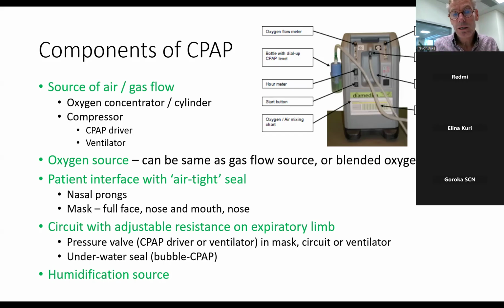You need a patient interface with a relatively airtight seal, and they can be, as I said, in adult CPAP, of course, you use a fairly tight fitting but soft face mask. It's got a cushion on it that fits the face reasonably well in most people. In children, we've been using nasal prongs, different sorts of nasal prongs, and I'll show you the three types that have been used, and I'll show you the ones that are being used mostly with these Diamedica machines. You need a circuit that is an inspiratory limb. A circuit is like a circuit of tubing, and there's an inspiratory limb that goes to the patient. So from the gas flow to the patient, the inspiratory limb, and then you need an expiratory limb that comes from the patient to the device that generates the CPAP.